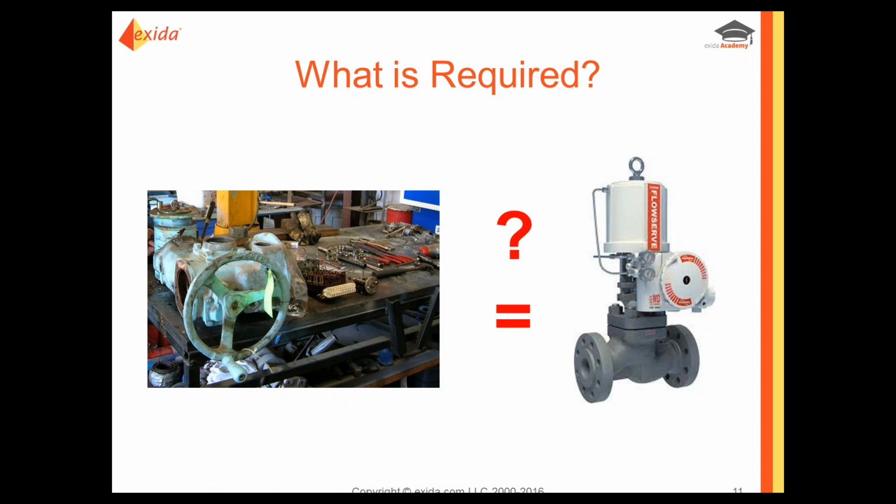Now, there's no prescriptive path in the standard saying that you must buy an integrated valve assembly or you can't do certain things, but there are requirements to show that traceability and to show a reasonable amount of evidence for verification and validation that the system will function correctly.